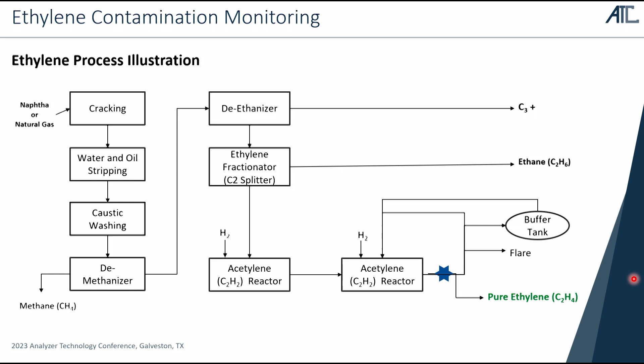So we'll present collecting data at the output of an acetylene reactor. This device gives us acetylene at an LOD of 2 part per billion with a sensitivity of 1.3. We define our LOD and our sensitivity as 2 or 3 times, depending which one, the zero gas baseline noise. And we could measure ammonia and water at the same time.